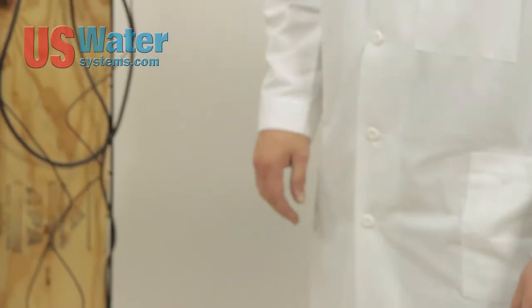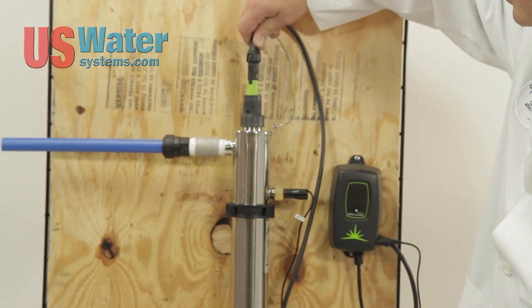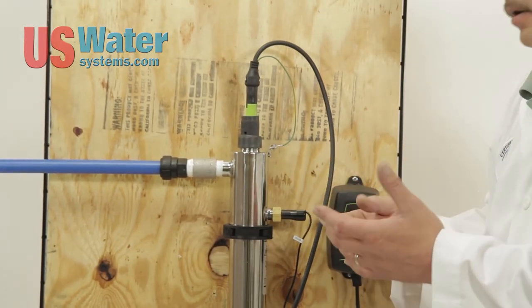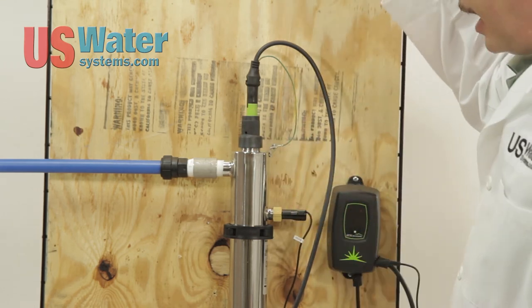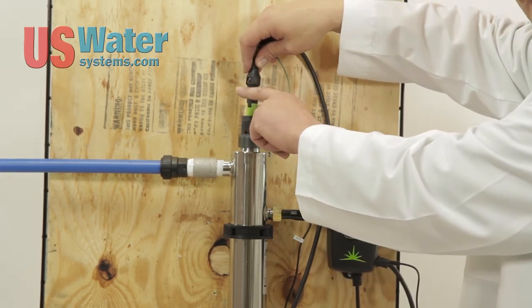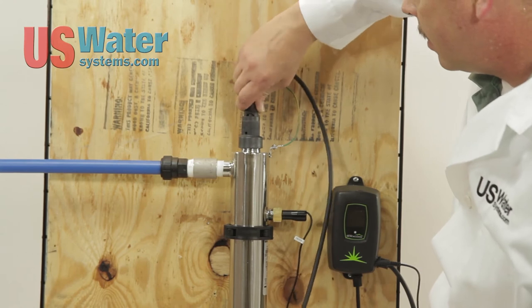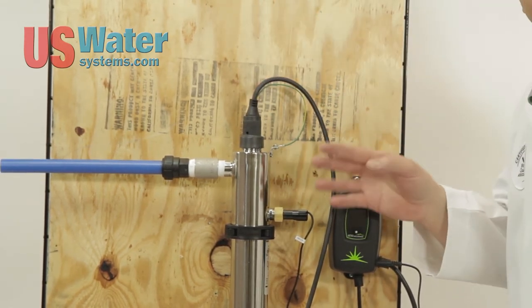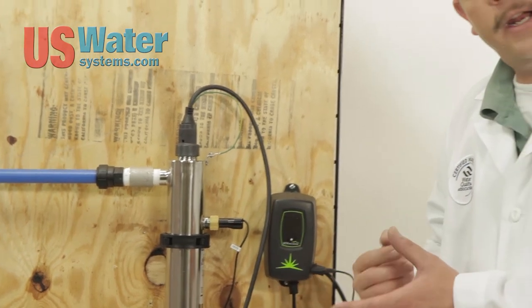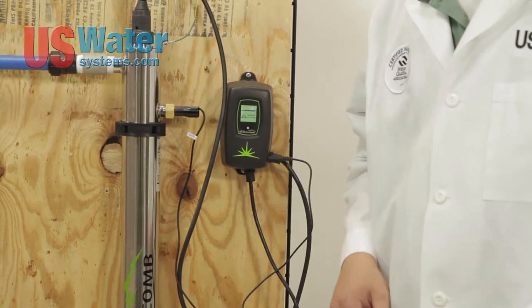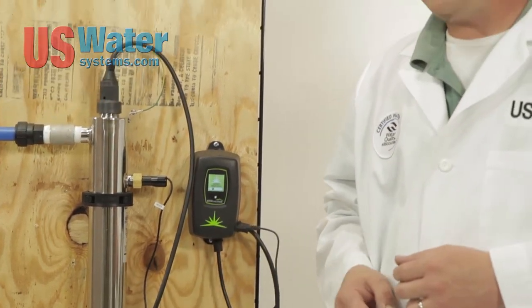To change the bulb, we're going to unplug the unit. Shut the power off. You're going to take the bulb out in the same reverse order. You're going to push down, turn, and let it up. Put your gloves on, remove the connector, pull the bulb out, put the bulb back in, put the connector back in, orient it with the tabs, then reinstall it. Once it's all reinstalled and attached and you're sure that you didn't accumulate any leaks or anything like that, then you'll just plug the ballast back in. It'll go through the diagnostics, detect the new bulb, and everything will go back to 100% and you're ready for another year of usage.